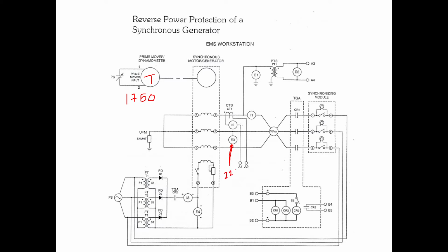Now we have to adjust this supply, and as we adjust the supply, you have to see these lamps. Slowly the lamps will dim. When all the lamps are off, we have to close this switch, not this switch. We have to close the synchronizing switch. We have to close all these switches.